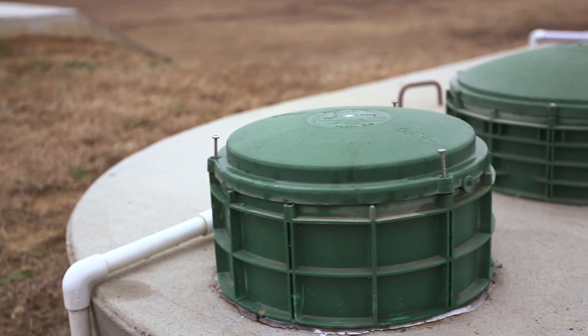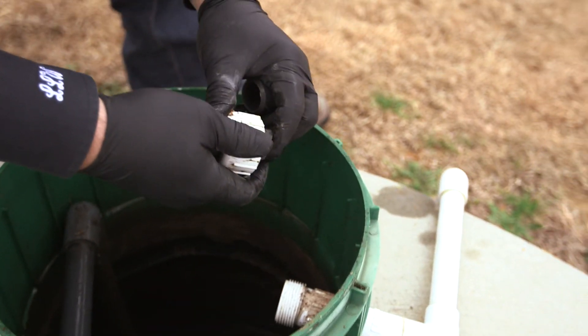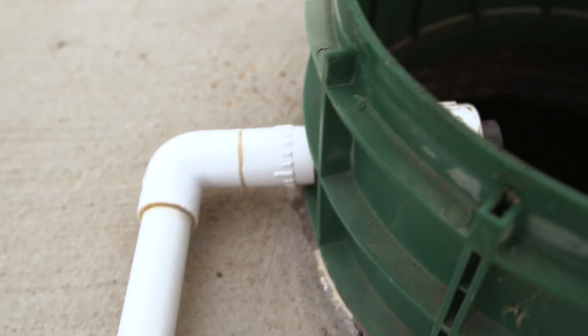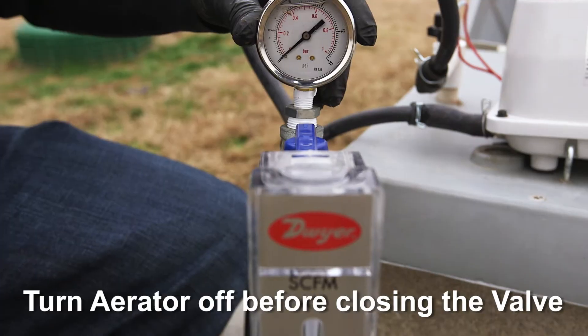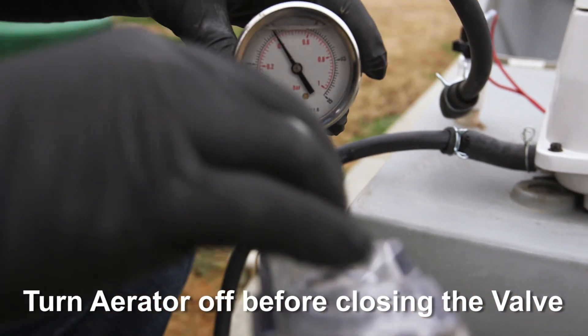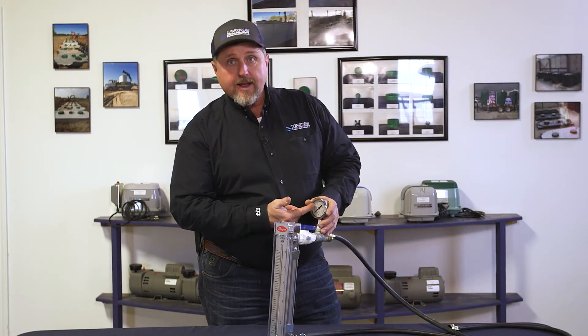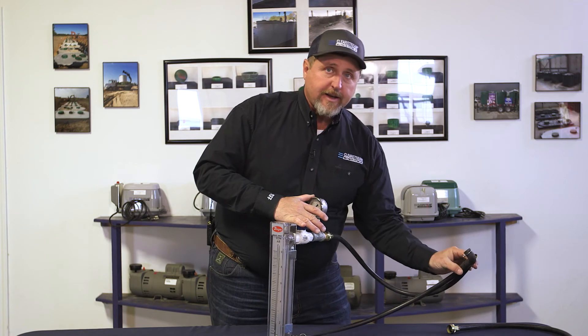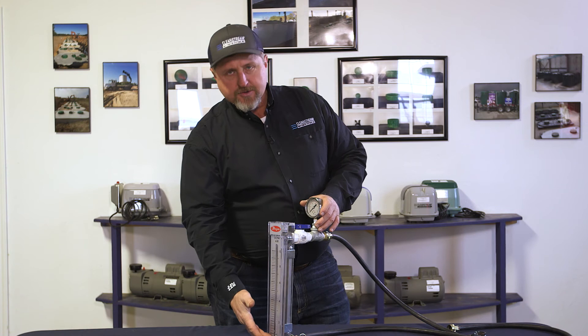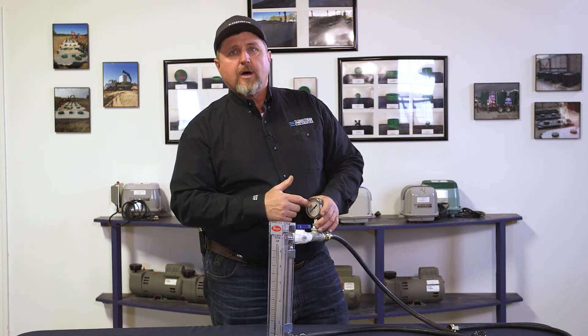When checking for a blocked airline, we cap the airline at the treatment plant. We come back, turn the air on, and let it build up to max pressure. We shut this valve — the needle should hold steady at our max pressure. If you see the needle streaking down, make sure you don't have a leak at your fitting, but that does indicate a broken airline. You could have the proper CFM in flow, but with a broken airline, it's not going all into our treatment plant.